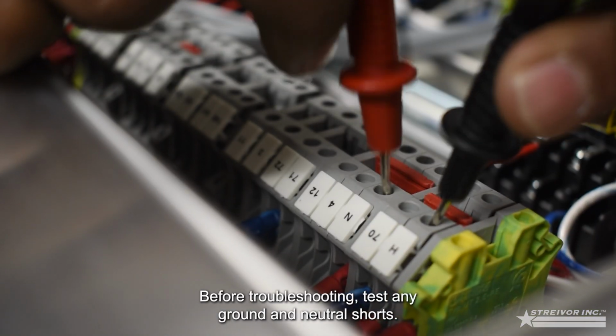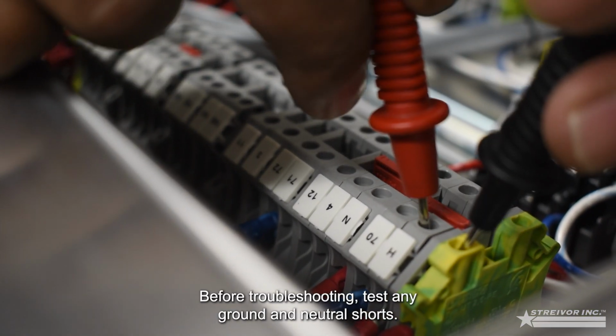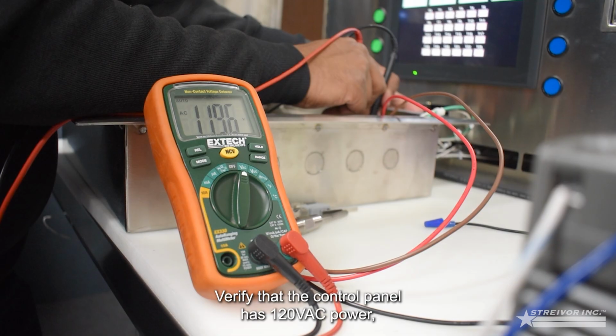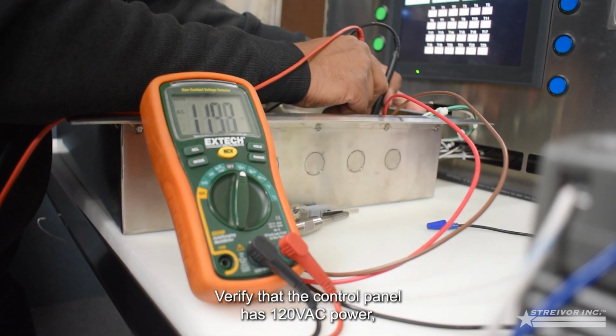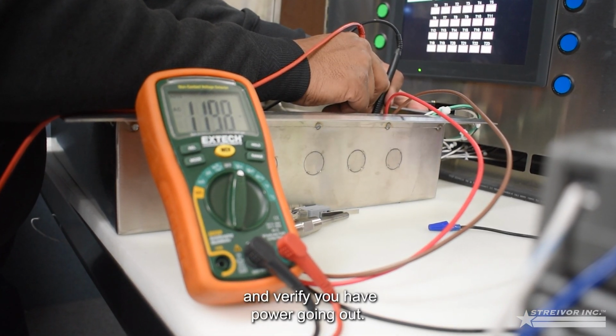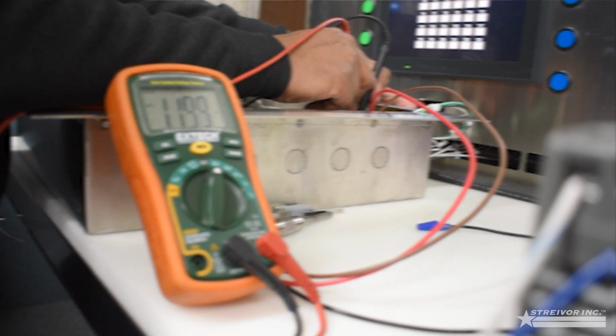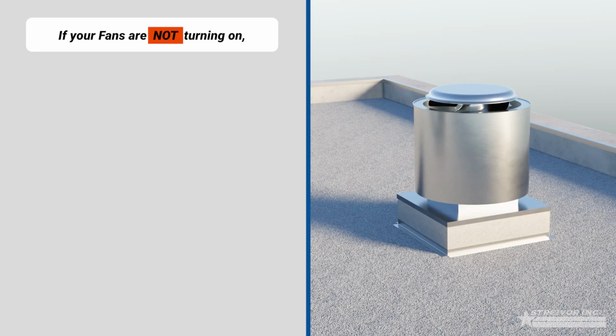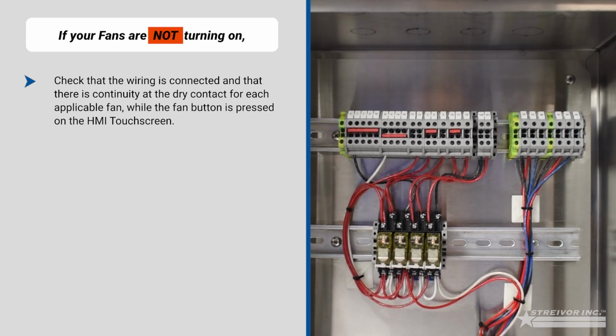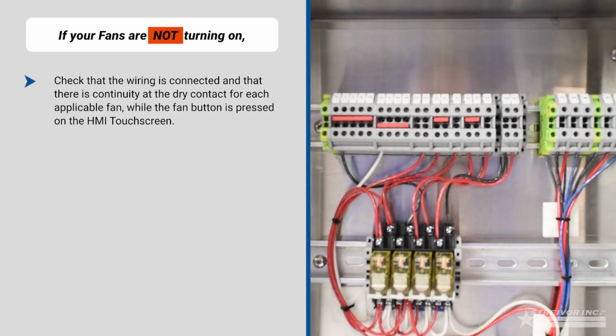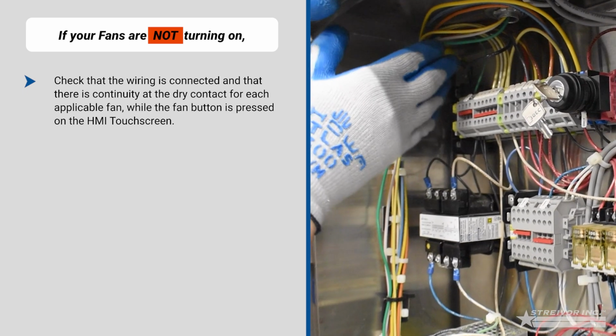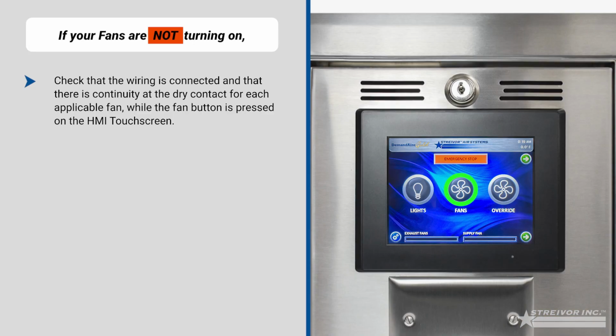Before troubleshooting, test any ground and neutral shorts. Verify that the control panel has 120 VAC power and verify you have power going out. If your fans are not turning on, check that the wiring is connected and that there is continuity at the dry contact for each applicable fan, while the fan button is pressed on the HMI touchscreen.